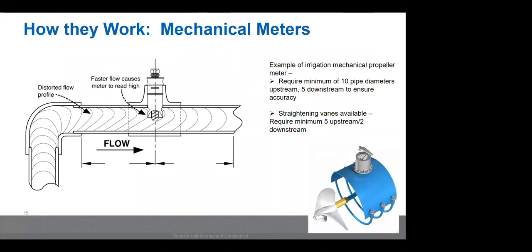Here's a popular propeller meter down here on the right-hand side. And this is just kind of an image that shows us what I'm talking about with the flow profile. As the water's coming through that elbow, it's moving pretty fast and it's swirling. It's causing that register to read high. So if your mechanical meter is installed without the proper upstream pipe diameter, it's going to cause you to read high, which isn't good because it's going to say you're using more water than you think you're using.